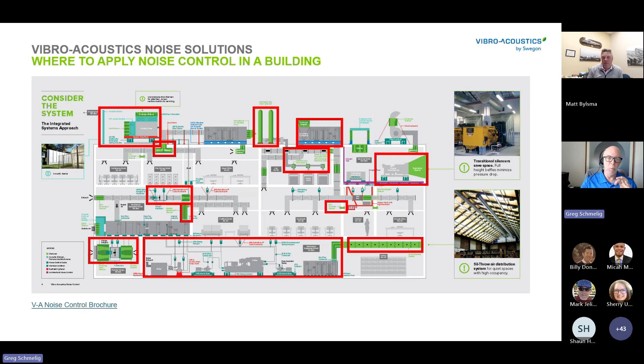What we do, and how we test: as an industry, as silencer providers, you have a number of manufacturers to choose from. We all test our silencers out of our catalogs to the ASTM E477 standard, the most recent version being the 2020 version. That standard tests for insertion loss—dynamic insertion loss, DIL—the acoustical absorption within each octave band that the silencer affords, along with its static pressure drop.